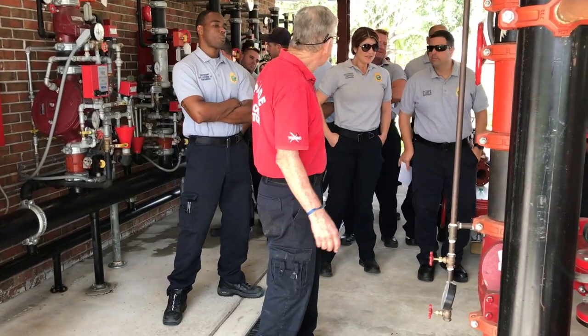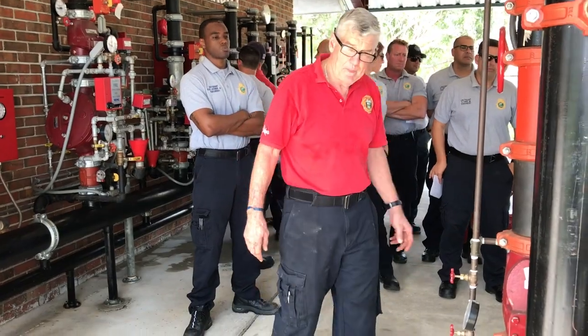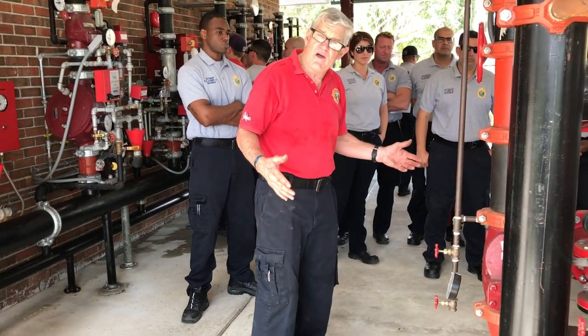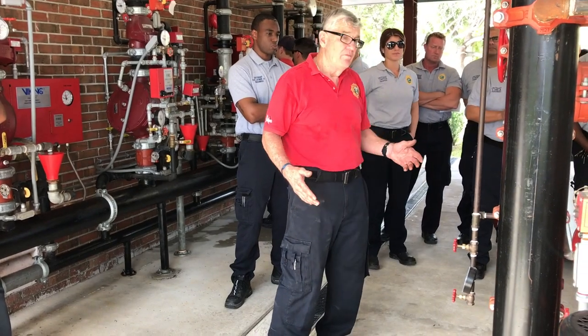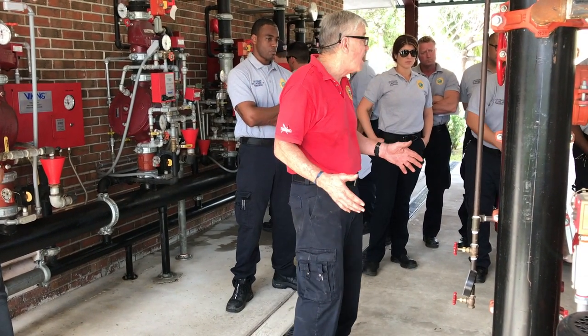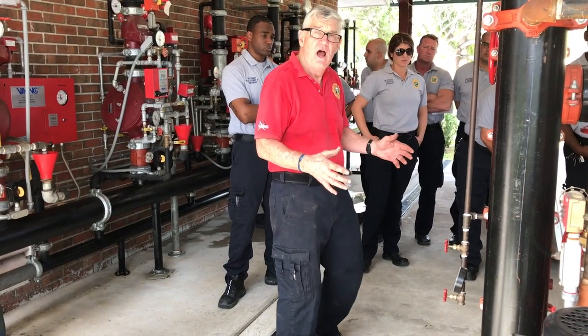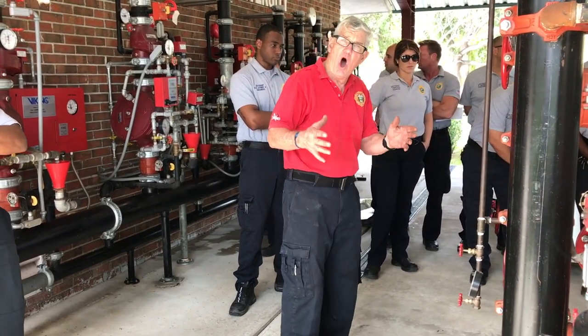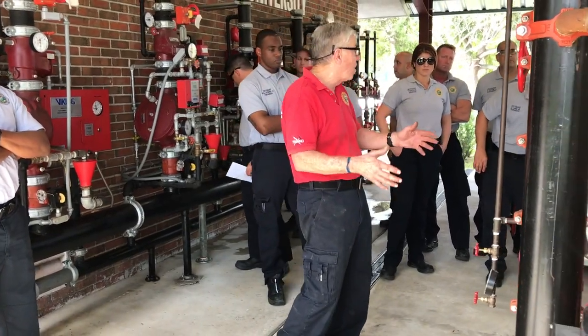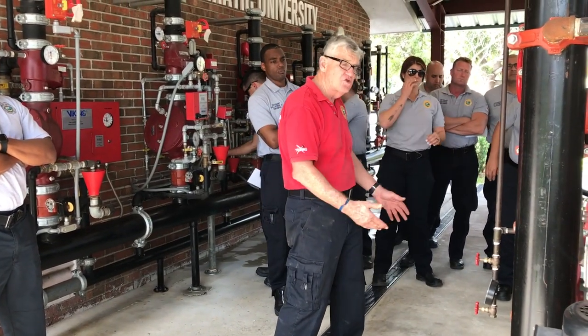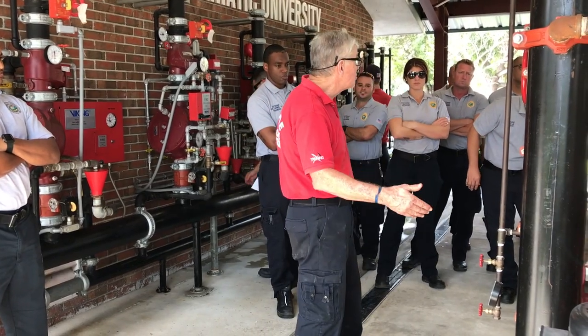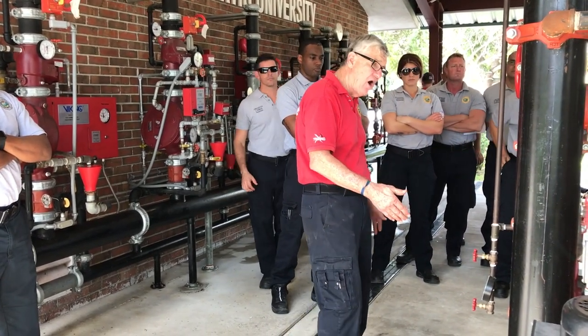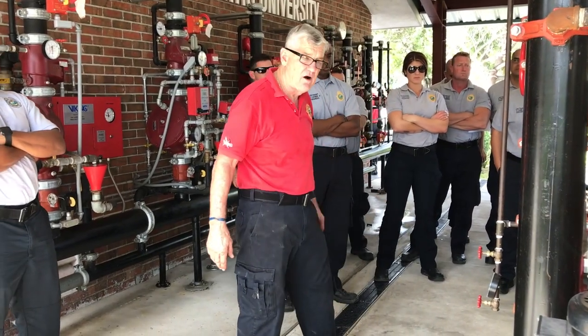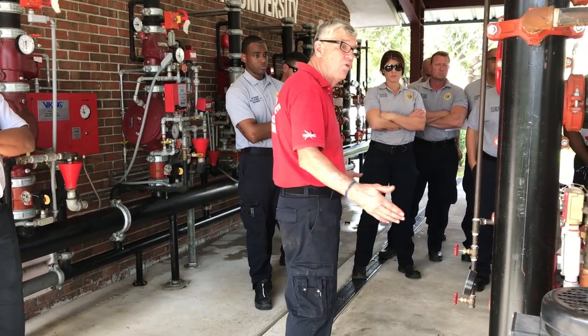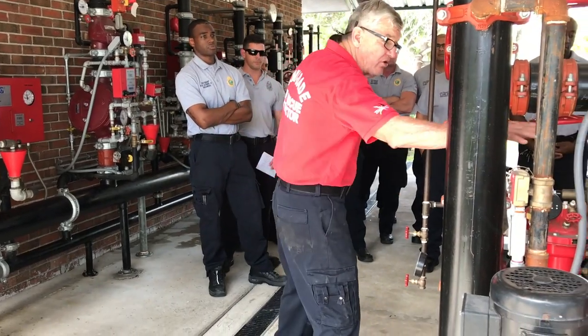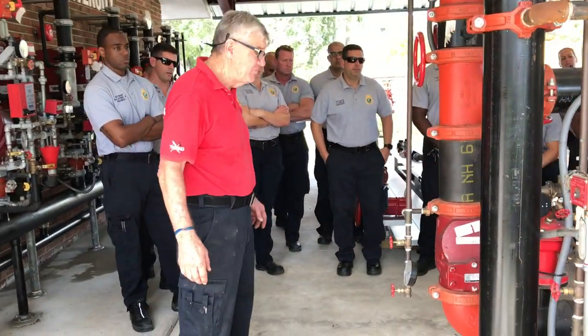This is the facility's diesel-driven fire pump. There are electrically driven, there are diesel driven. Electrically driven fire pumps are commonly backed up by a generator and what we call an automatic transfer switch. If the power goes out to the building, the transfer switch kicks in, starts the generator, and transfers the generator power to the electric motor that drives the fire pump. Pump is very similar to what we have in our fire apparatus. So in this case, this is a diesel engine.